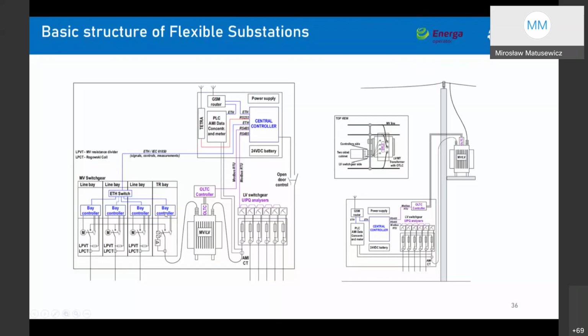This is common to both the pole flex station and indoor flex station. Of course, for the indoor flex station, the next step is the medium voltage switchgear, a typical medium voltage switchgear with line bay and transformer bay. What's different is that each bay is equipped with a bay controller, not one controller for the whole station, and the connection with the central controller, which is the heart of the flex station, uses the IEC 61850 protocol.